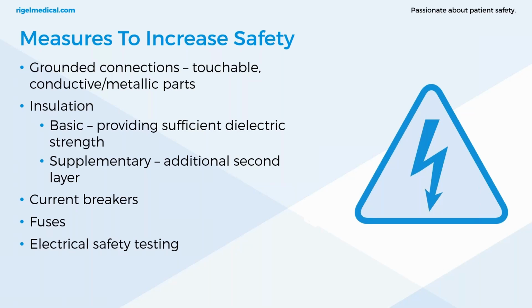Any large fault currents are going to flow down that very low resistance path rather than through a patient or user. In addition to that, you have RCDs, current breakers, which will interrupt any voltage supply if hazardous leakage is detected on that ground path. So it's got two methods of protecting the patient. One is by removing that current away from the individual, but also by tripping the current breakers, RCDs, etc.